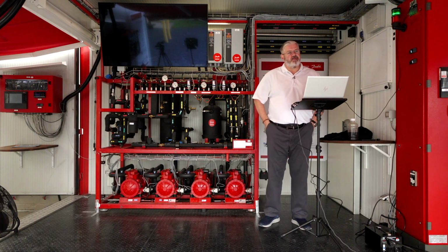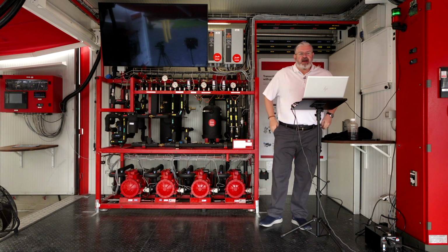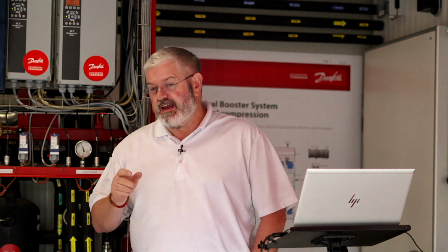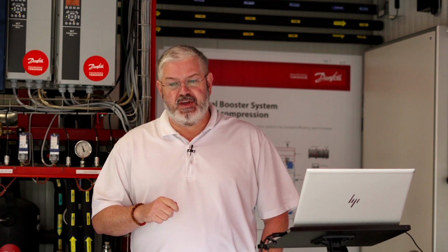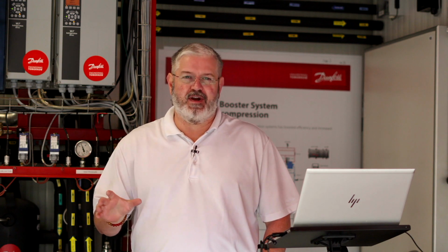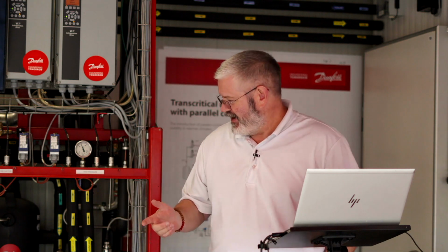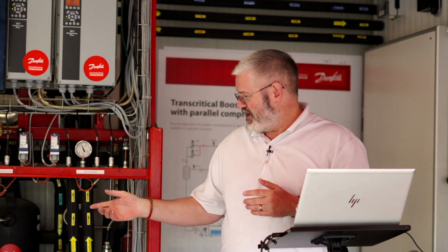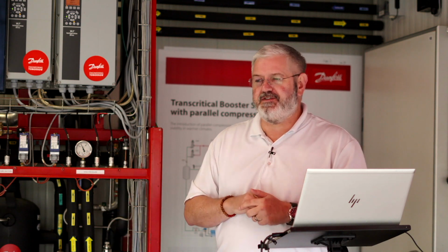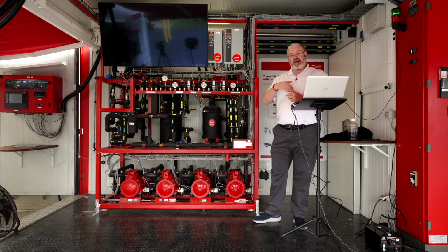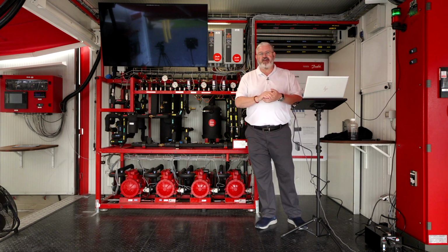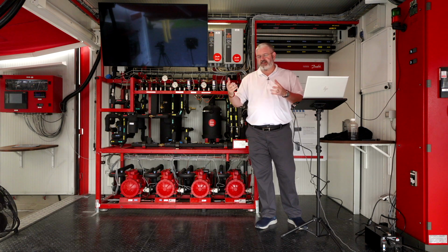So it says, what are some of the most common service issues with CO2 systems? I can't really speak to the service issues. That's not really my forte. However, I can speak to the startup side, and I see people struggle with the oil. Everybody knows if there's an oil problem, you need to dump in 2 more gallons, or that's the common misconception. It's pretty common. People put in more oil than they should because the pressure switch wasn't defined correctly. There's some other issue, and they wind up having to take that oil back out of the system. So I see people struggling to get the oil portion right. And then service-wise, I don't run service in that way. I kind of support startups and things like this. So I don't have a good answer, and I'd rather be honest.